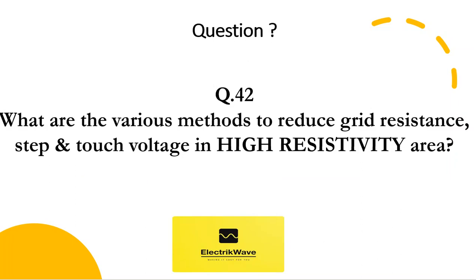Question number 42: what are the various methods to reduce grid resistance, step and touch voltage in high resistivity areas? Sample answer 42: various methods are in practice to reduce grid resistance; however, their application depends on soil conditions and will vary site to site. Method 1 — basic methods for decreasing grounding resistance: increasing the grounding grid. The ebook link is given in the description box — download it and get ready for the interview.